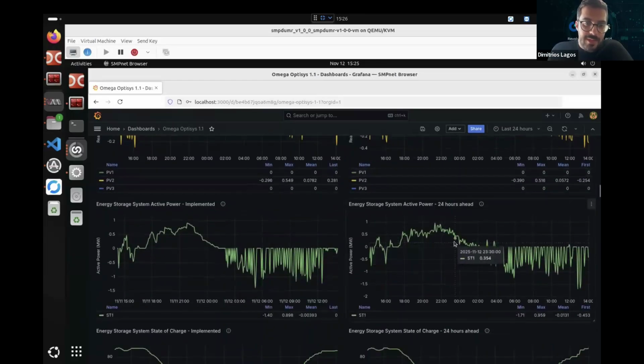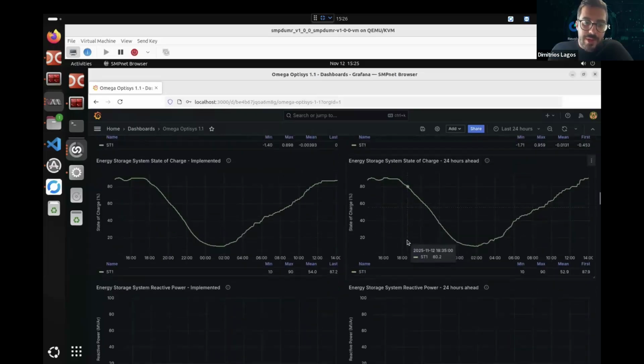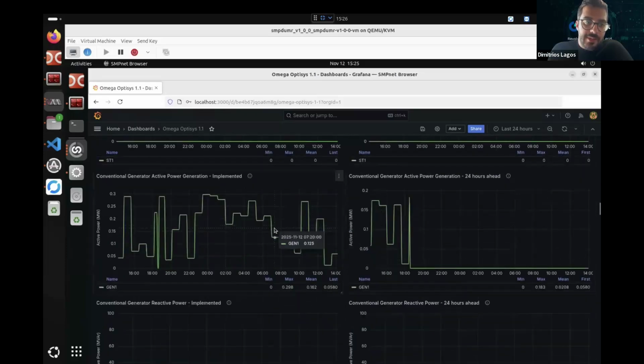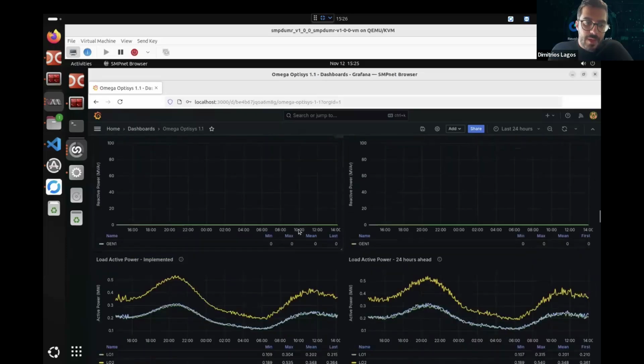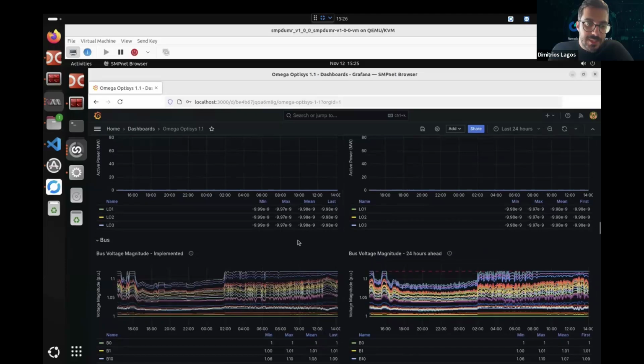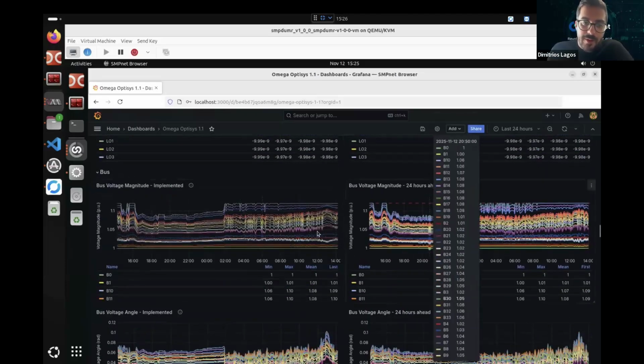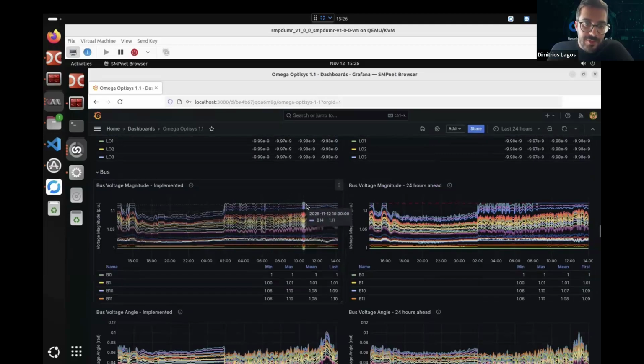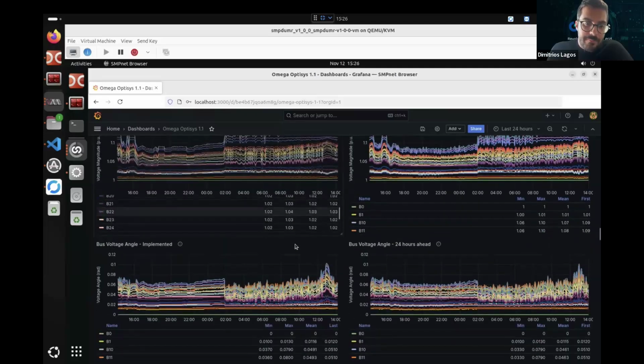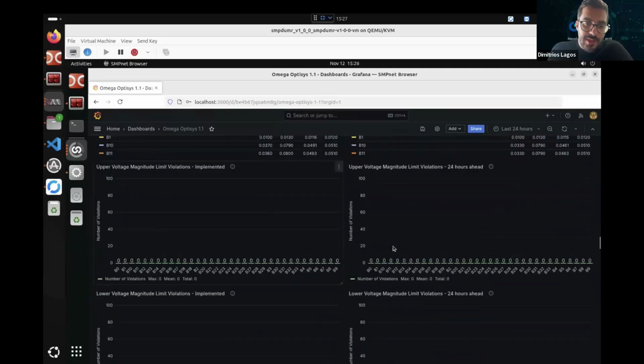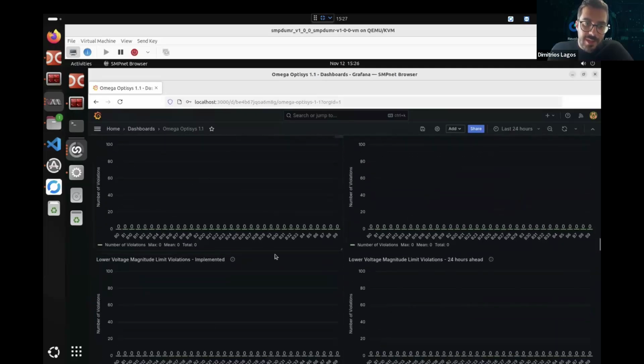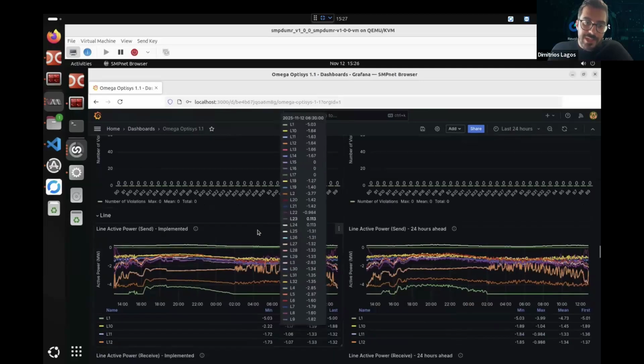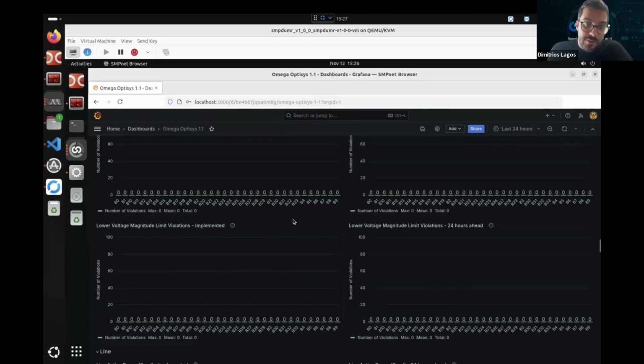Also here we see the energy storage system, the active power and state of charge evolution throughout the day, and the generator active power. There is also a thermal generator in the model. Apart from that, Optisys also calculates the voltage profile for the next 24 hours. We see, for example, that there is a voltage limit in this system of 1.12. That's why in this time period we saw reactive power dispatch and active power curtailment to resolve the voltage issues. Let's continue. If there was a voltage violation in these graphs, we would see in which bus and for how many minutes the limits have been exceeded. Now we see that with the Optisys dispatch, we do not have any violation in the voltage.